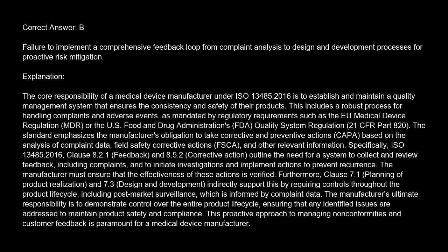This includes a robust process for handling complaints and adverse events, as mandated by regulatory requirements such as the EU Medical Device Regulation, MDR, or the U.S. Food and Drug Administration's FDA Quality System Regulation, 21 CFR Part 820. The standard emphasizes the manufacturer's obligation to take corrective and preventive actions, CAPA, based on the analysis of complaint data, field safety corrective actions, FSCA, and other relevant information.